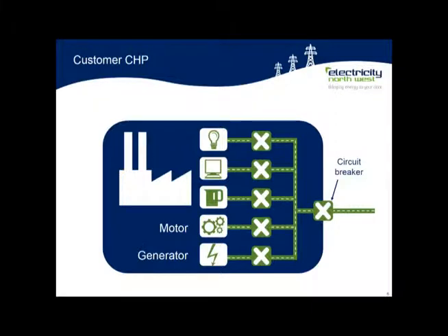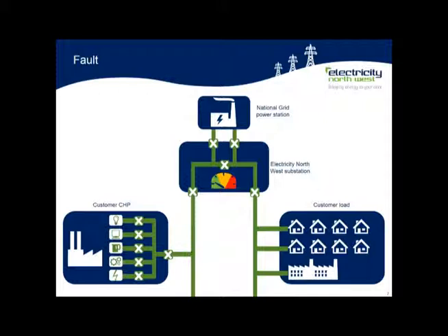When a fault occurs, fault current from all the connected sources of generation, including the customer's generator and motor, surges towards the point of fault on our network. This is similar to the flow of water you experience when the water pipe is burst. You can see in this example the dial at our substation has moved from green to amber. This indicates the change from load current to fault current, but fault current at a level that is still safe and can be managed by our network equipment.